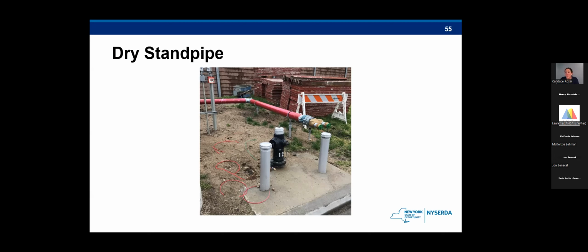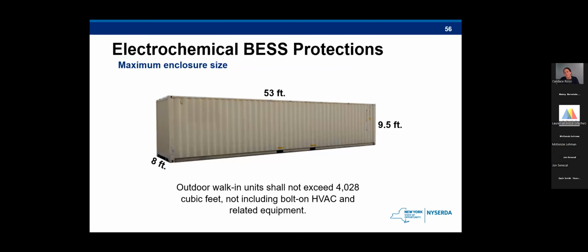The pipe is in place permanently with an intake, usually located near a road or a driveway, so that the fire engine can supply water to the system. The standpipe supply pipe extends into the container to supply firefighting water to the interior of the structure via those hose outlets. And dry standpipes are not filled with water until needed. So firefighters often are the ones bringing in the hoses and attaching them to these outlets to basically flood the inside of the container. This is not always possible for every installation, as you might not have the water supply that's able to utilize that, but it's definitely something to consider.